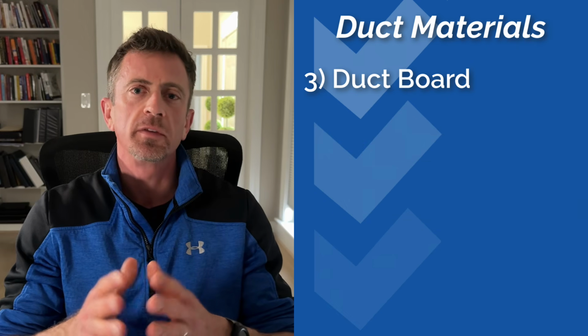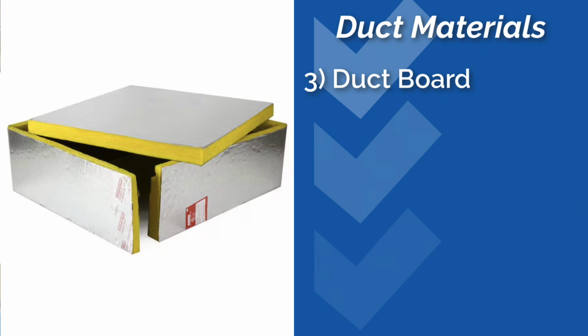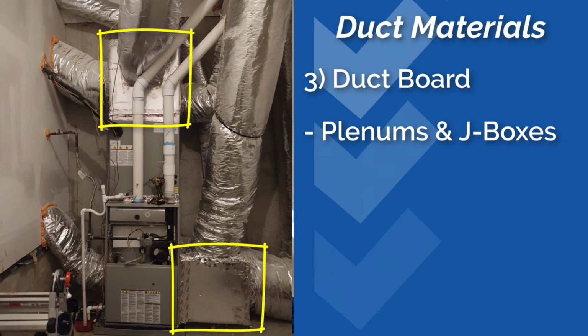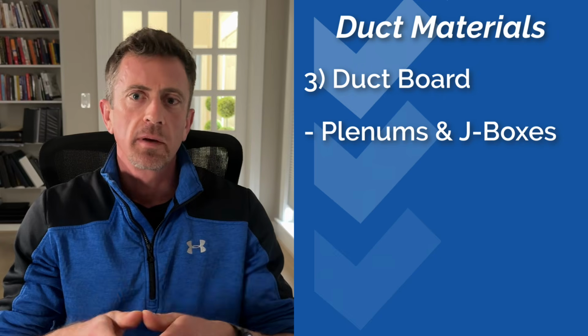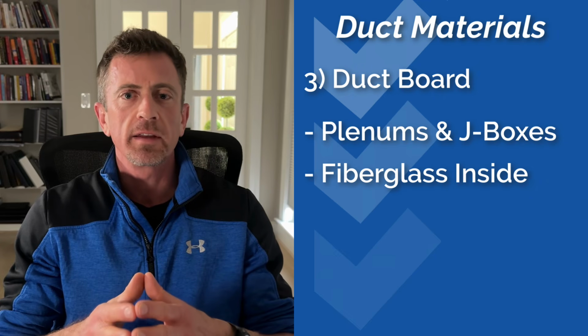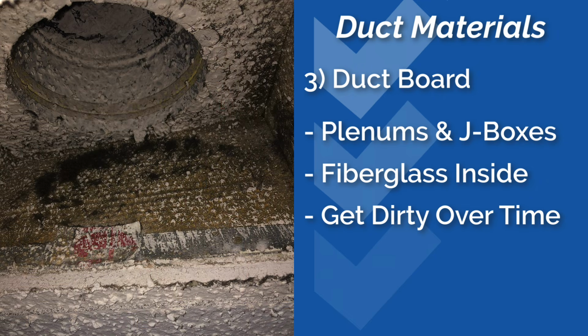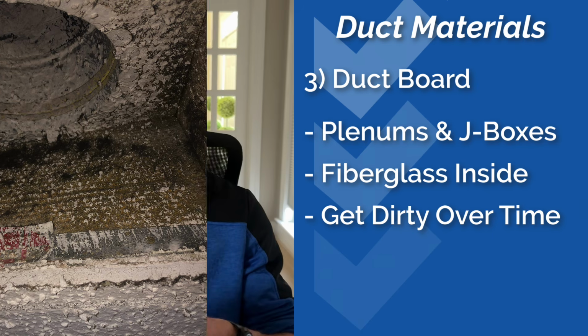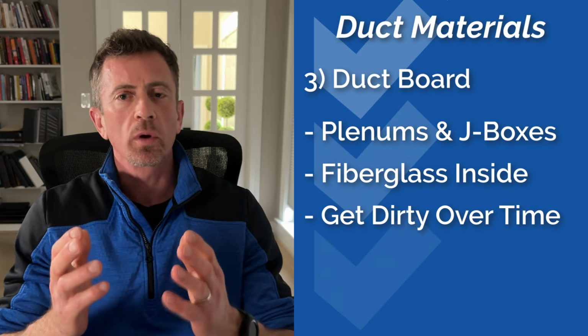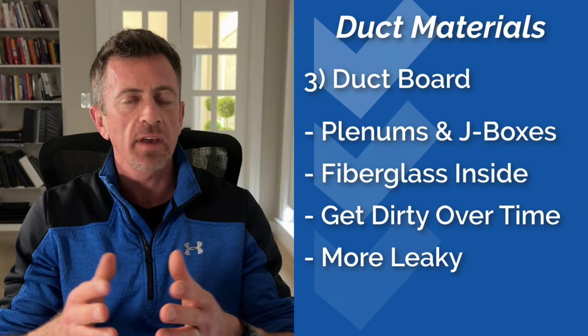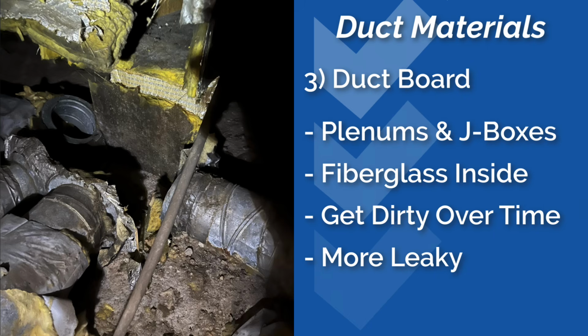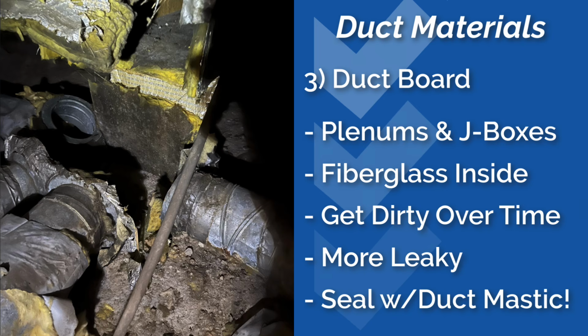The next material up is duct board. Duct board is made of dense fiberglass wrapped with a foil material. They're often used for supply and return air plenums and junction boxes. Because the fiberglass is exposed on the interior side, they can get really dirty over time, collecting dust and other junk that moves through the air inside your home. Ductboard also tends to be more leaky than other types of ductwork and tends to separate over time as well. This usually happens when cheap metal tape is used to seal the ductboard together instead of a thick layer of duct mastic, which lasts much longer.